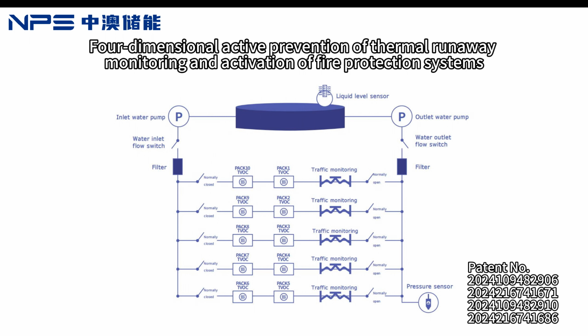We pioneered a four-dimensional active fire monitoring system for detecting and responding to battery thermal runaway. The system determines the gas composition in the battery box in real time by building a TVOC monitoring probe into the shared gas path inside the battery box.